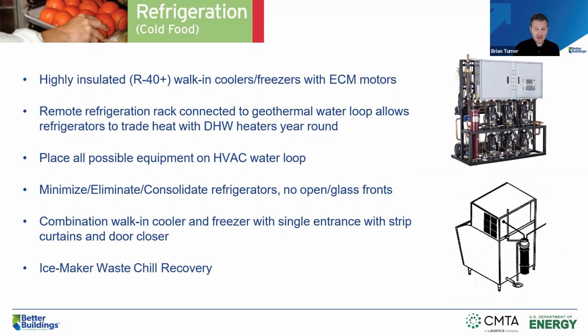Another strategy for a lot of our zero energy projects and high performance projects, we've got water source loops for the cooling, often at the heat pump loop, so it's neutral temperature water. You can use water source compressors for a lot of refrigeration equipment, not just the walk-in coolers, but even smaller reach-in coolers, ice machines, even serving equipment. And if you put those on the geothermal loop, they can reject their heat to the geothermal loop where it can be recovered to be used for things like water heating.